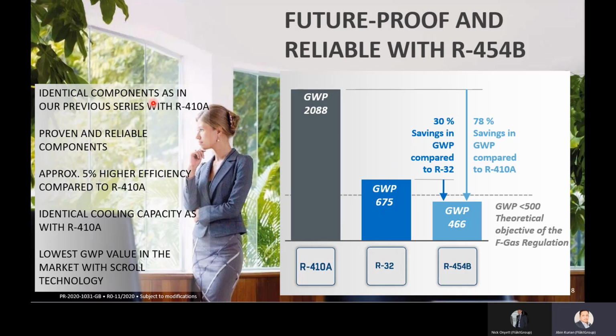So compared to R410A, R454B is 78% lower in GWP, and compared to R32 there is a 30% saving in GWP. So this is one of the best available in the market. And we use identical components as the previous series with R410A. By using R454B, the chiller efficiency has gone up by approximately 5%, with identical cooling capacity to R410A. So this is the best in class available with scroll technology.